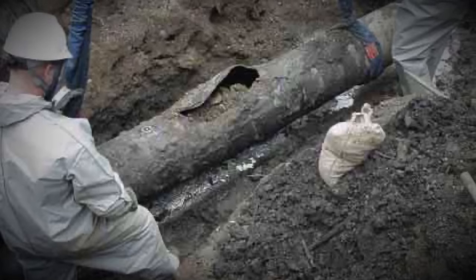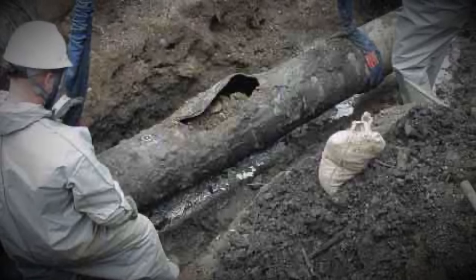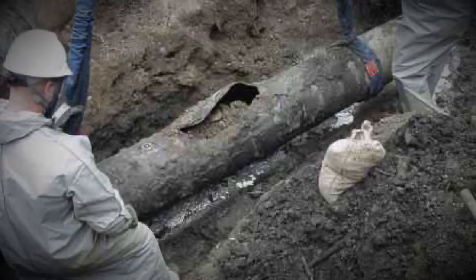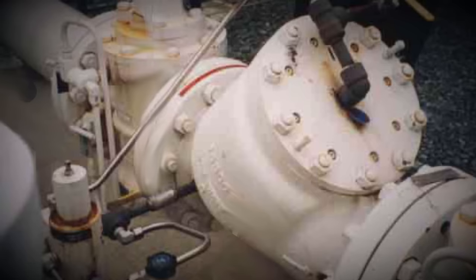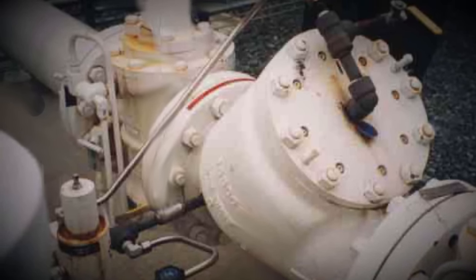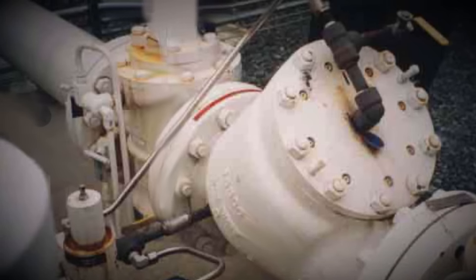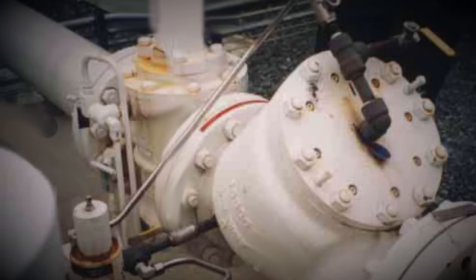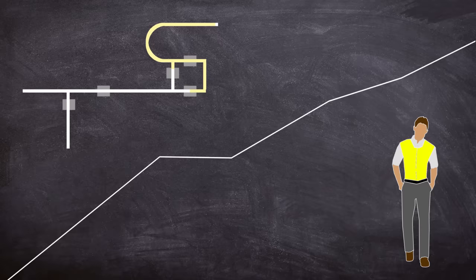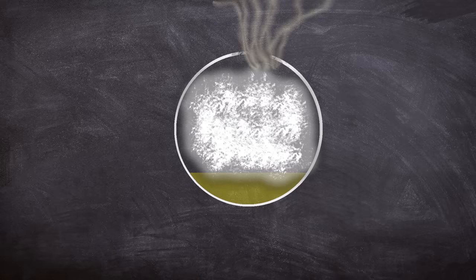Investigators found that the cause of the rupture was due to multiple failures stemming from the initial damage to the pipeline, but the disaster could have been averted with proper investigation into the damage. But the failure goes much deeper than that, as the way Bayview was brought online with the malfunctioning relief valve led to extended times of high pressures within the network, which in turn caused the damaged section of the pipeline to rupture. The warning signs of the block valve repeatedly closing were not rectified by Olympic. This problem was further compounded with the actions of pipeline staff, undertaking database development work on the SCADA system whilst it was being used to control the pipeline, leading to a complete system failure. With the system unresponsive and the block valve closing, pressure surges found the path of least resistance, the damaged section of the pipeline, which resulted in catastrophic structural failure and ignition.